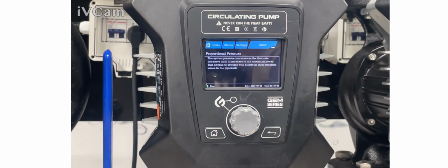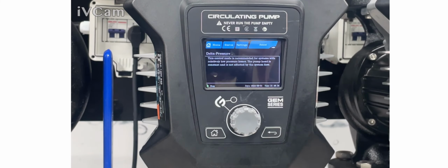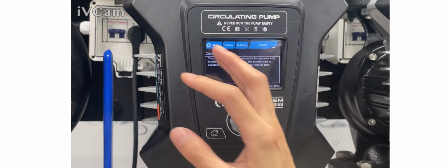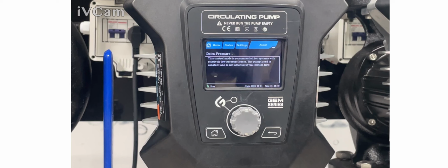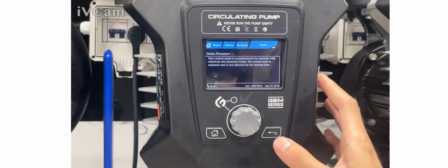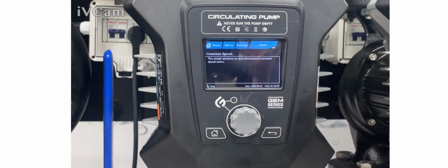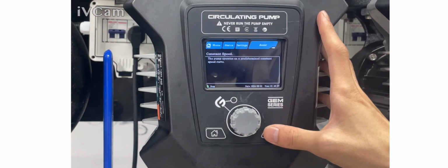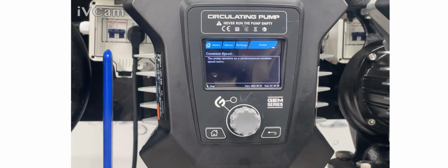And now it's our proportional pressure. The system pressure increases as the flow rate increases until it reaches the max power. This applies to systems with relatively large pressure losses in the pipework. And the next is our delta pressure. This control mode is recommended for systems with relatively low pressure losses. The pump head is constant and is not affected by the system flow. So the last is the constant speed mode. The pump operates at a predetermined constant speed curve.